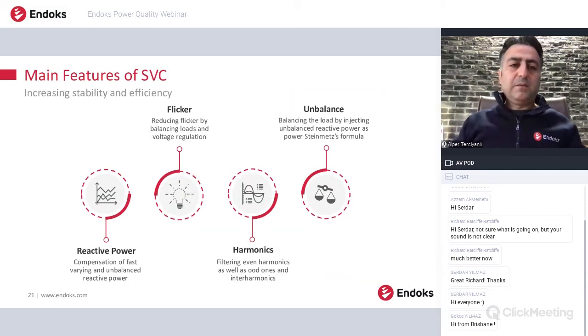And what are the main features of the SVCs, static var compensators? First of all, reactive power compensation. And the second one is reducing flicker. The flicker is generated mostly by very fast and varying loads like induction furnaces or arc furnaces. So the SVC can work very fast and also can generate unbalanced reactive power, so it can reduce flicker.